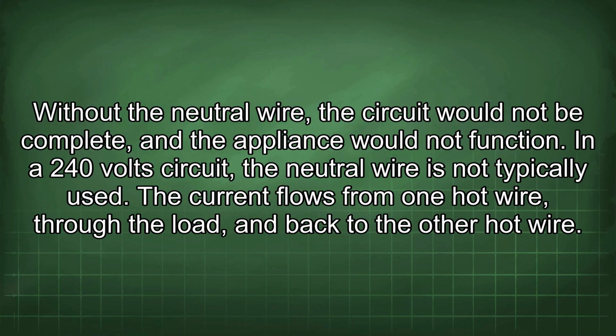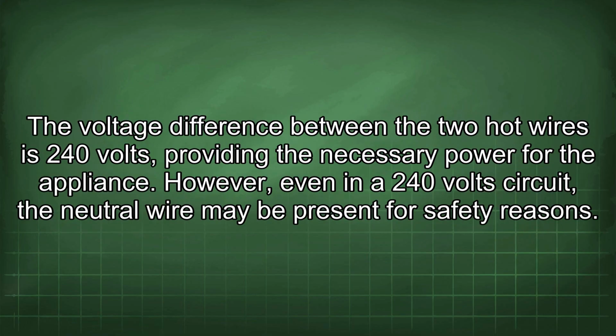In a 240 volt circuit, the neutral wire is not typically used. The current flows from one hot wire through the load and back to the other hot wire. The voltage difference between the two hot wires is 240 volts, providing the necessary power for the appliance. However, even in a 240 volt circuit, the neutral wire may be present for safety reasons.